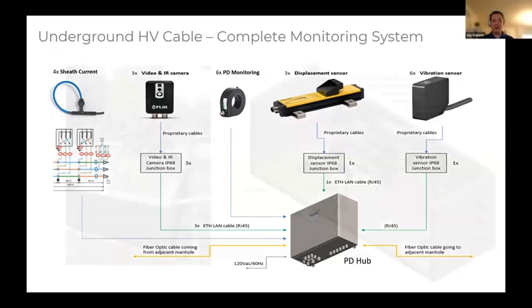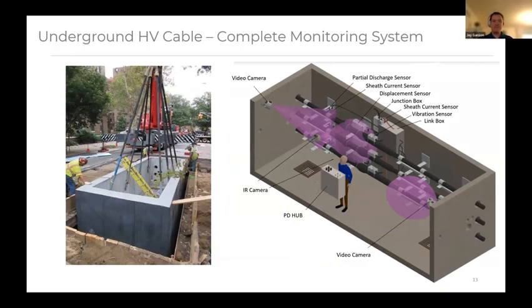So conceptually, what it looks like is, inside of that manhole vault, we have the infrared sensor right in the middle pointing at the cable splices, video cameras on either side to give live video feeds for inspection or other purposes, and a series of sensors mounted, once again, all in IP68 rated boxes throughout the system to provide that vibration, displacement, and other sensing. And really the goal is to say, how can we take other operational expense about owning and operating these cables and integrate it into that asset health system?